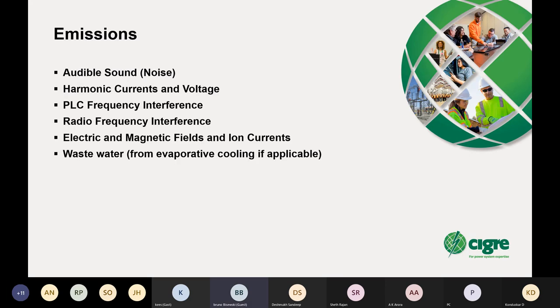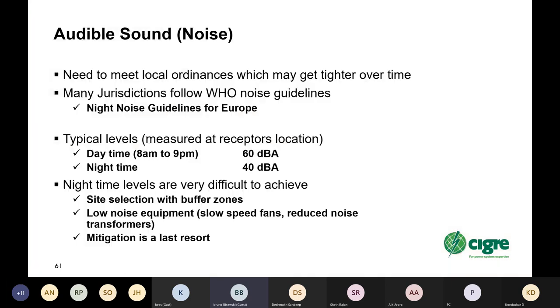Anyway, so some major emissions that need to be specified: audible sound or noise, harmonic currents and voltage, PLC frequency interference, radio frequency interference, electric and magnetic fields and ion currents, wastewater from evaporative cooling, if applicable. Usually you don't have evaporative cooling. It's not specified except in very hot climates. If it is provided, then you need to deal with some issues which we'll go into.